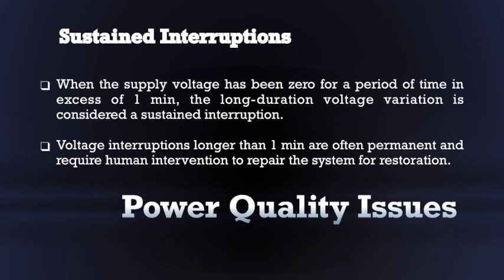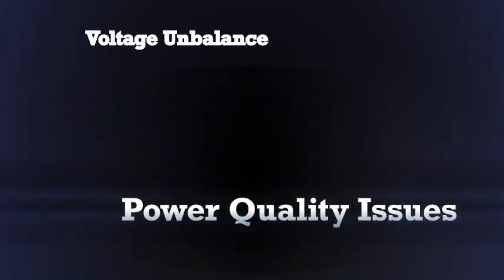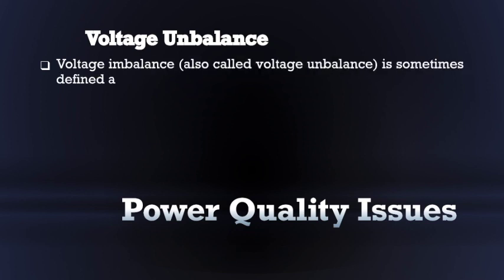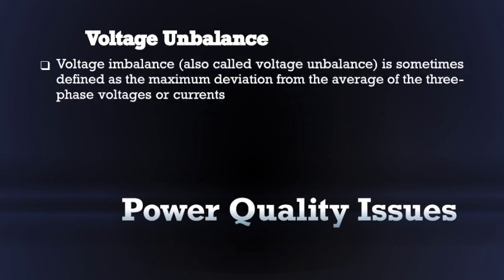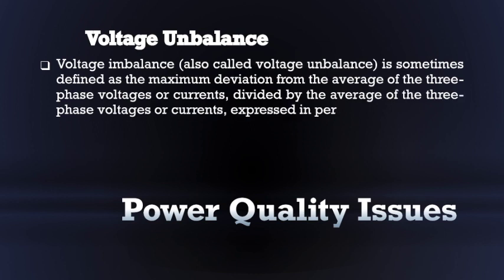If the time duration is less than 1 minute, it is considered an interruption and it comes under short duration voltage variations. When it exceeds 1 minute, it is considered a sustained interruption and it comes under the category of long duration voltage variations. Now, voltage unbalance. Voltage unbalance, also called voltage imbalance, is sometimes defined as the maximum deviation from the average of the three-phase voltages or currents, divided by the average of the three-phase voltages or currents, expressed in percent.